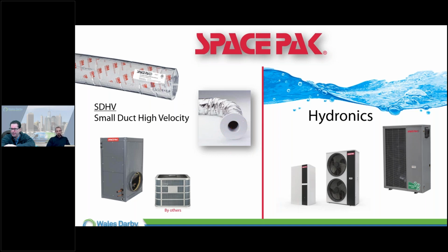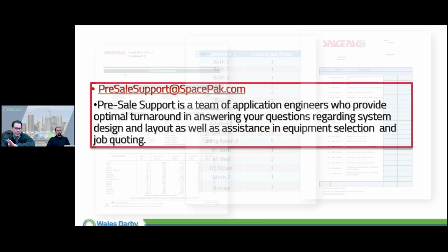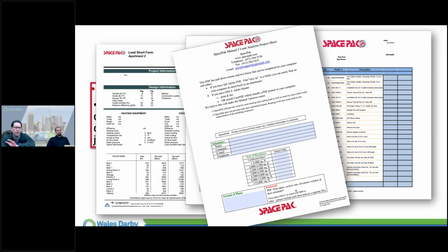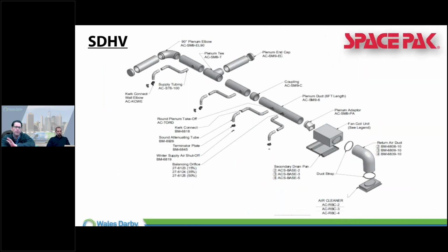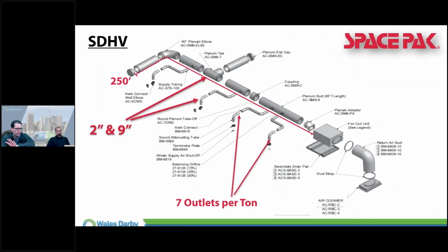As another tidbit, if you go around and find a noisy system, take a flashlight and shine it up in that outlet. You want to see a white gauzy material, that's where you know sound attenuators were installed. If you see shiny metal, either the sound attenuator is on the wrong side of the plenum, or it's not installed at all, because there's a cost to that. Sometimes people take out the material designed and engineered for quiet systems, and that's the downfall.